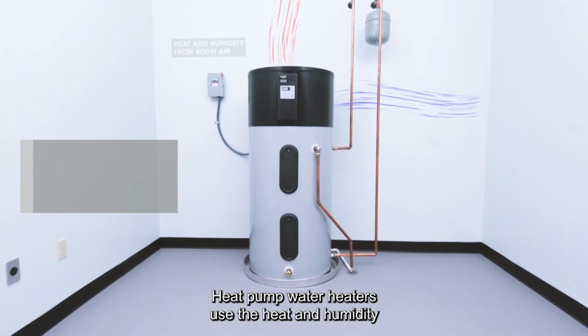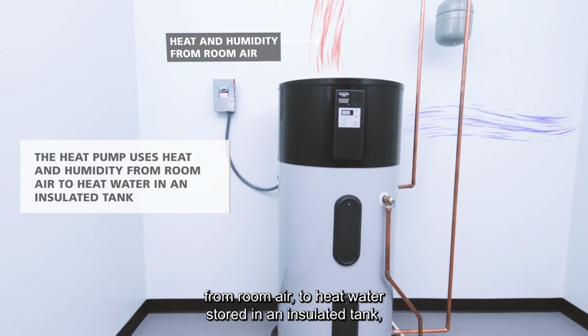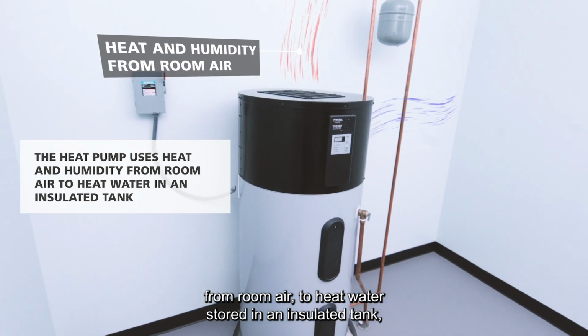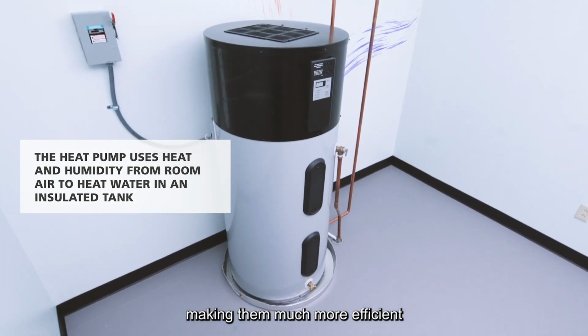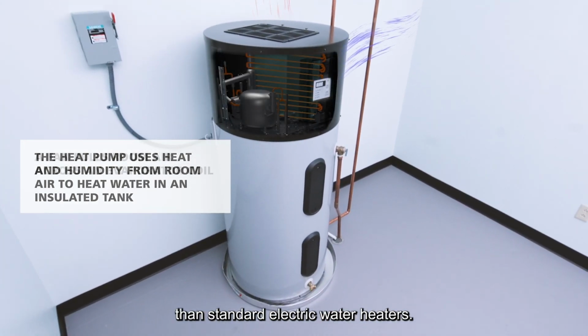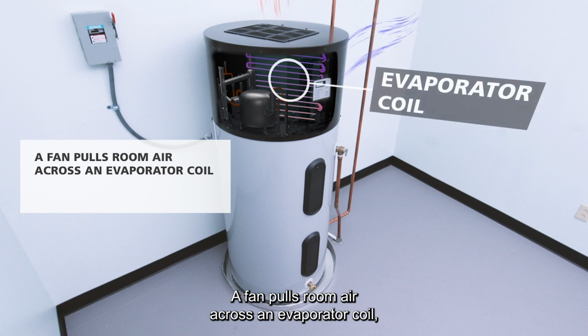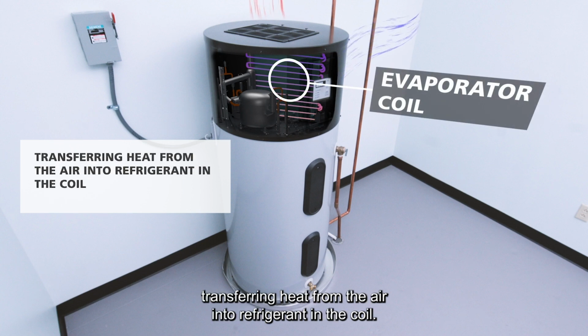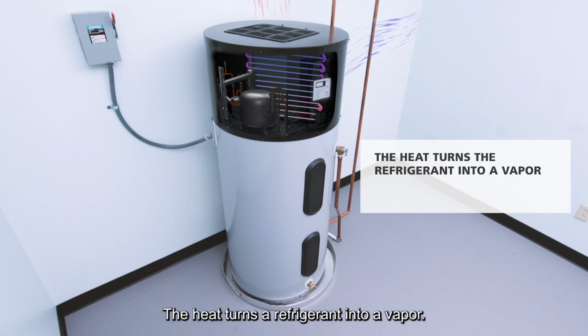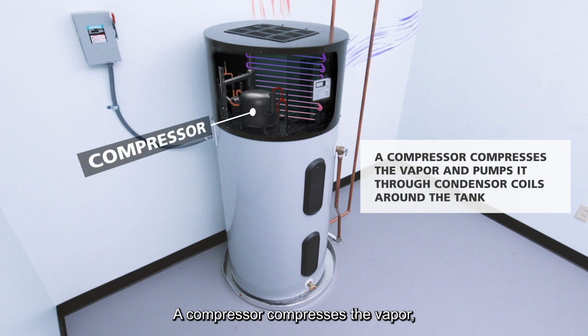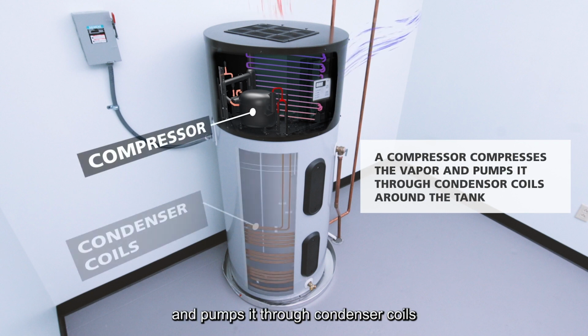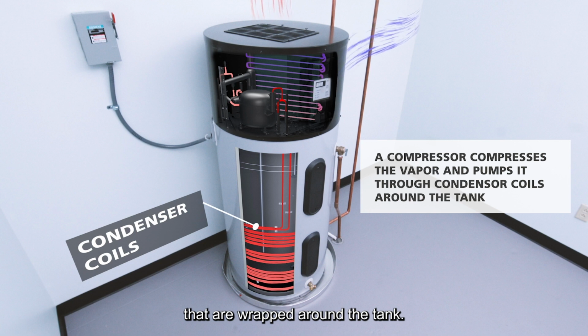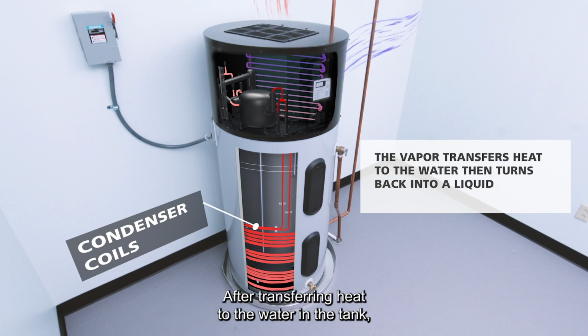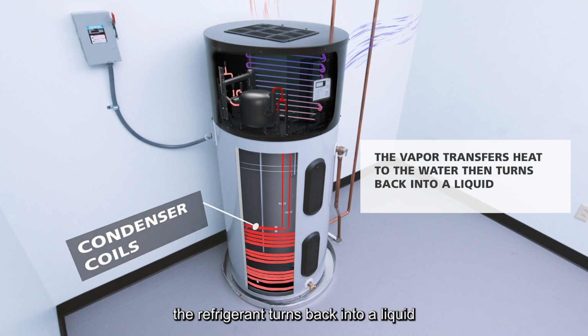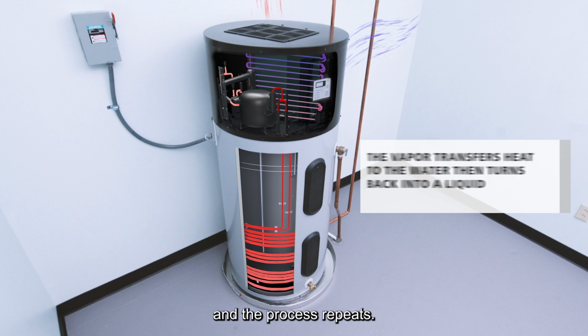Heat pump water heaters use the heat and humidity from room air to heat water stored in an insulated tank, making them much more efficient than standard electric water heaters. A fan pulls room air across an evaporator coil, transferring heat from the air into refrigerant in the coil. The heat turns the refrigerant into a vapor. A compressor compresses the vapor and pumps it through condenser coils that are wrapped around the tank. After transferring heat to the water in the tank, the refrigerant turns back into a liquid and the process repeats.